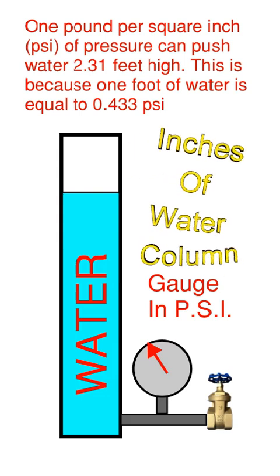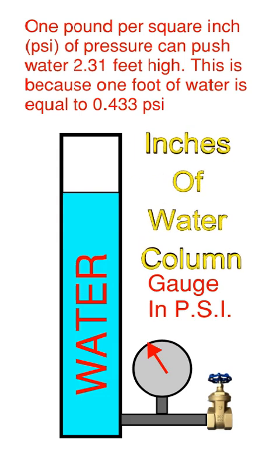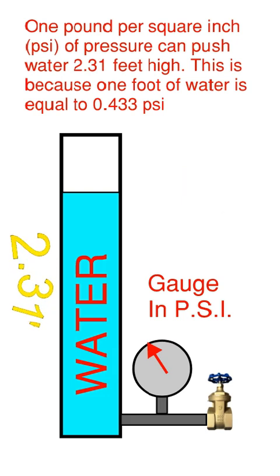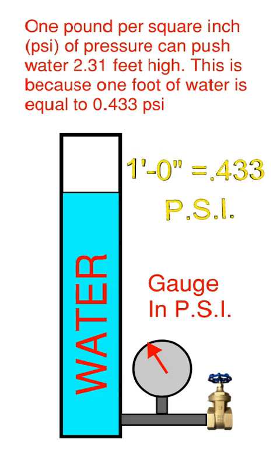Before we get into that, we need to understand that one pound per square inch of pressure can push water 2.31 feet, and that is based on one foot of water equals 0.433 static head pressure.